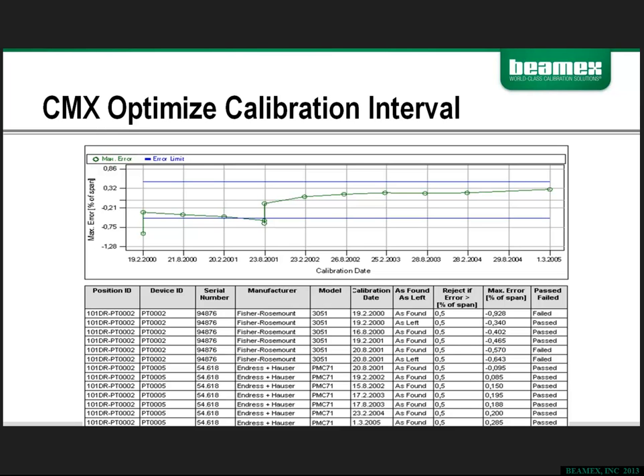And basically, that was over a 3-year period. The unit passed every calibration. So the end user, if you look towards the bottom, actually adjusted that interval to a year versus 6 months in February of 2004. And in March 2005, that unit had very little drift and was still serviceable and very well in tolerance.